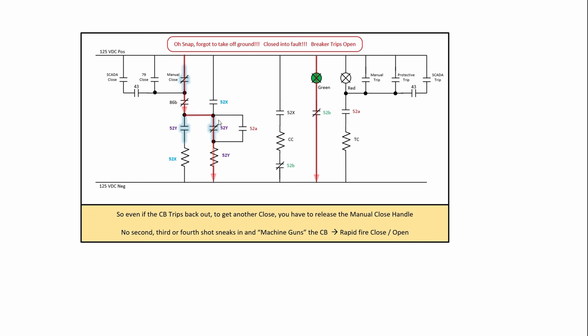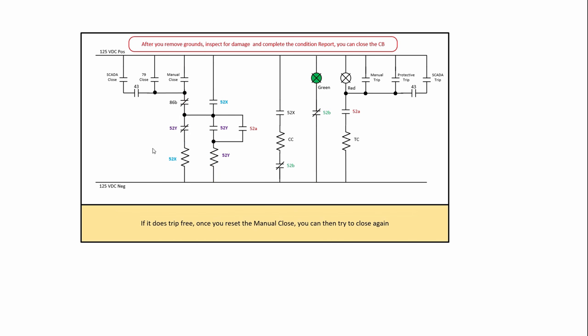Now again, if you didn't have this 52Y in there, that thing would come through and you would just come right back in and hit that 52X or if you didn't have anti-pump logic, you'd just hit the closed coil. So now you remove the grounds, inspect for damage and then complete your condition report and close the circuit breaker again. Now, let's look at some troubling areas.